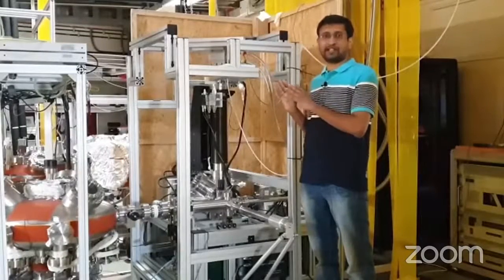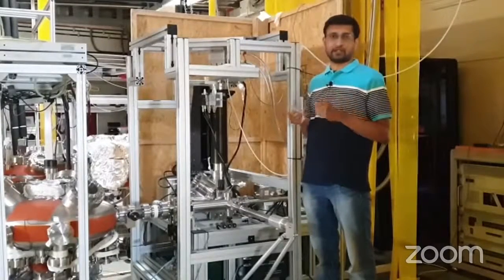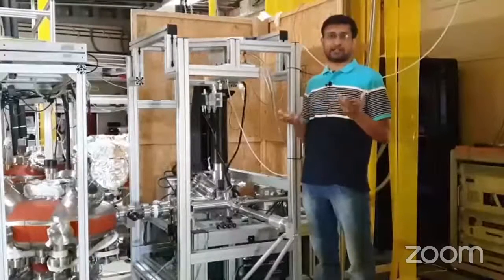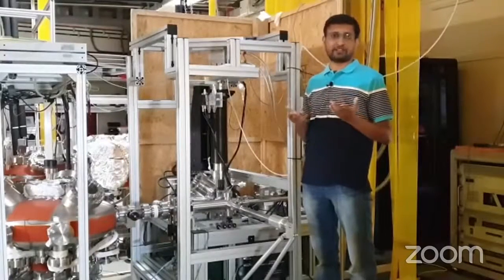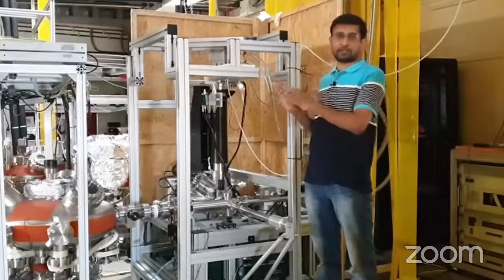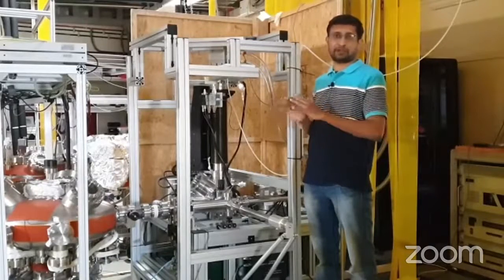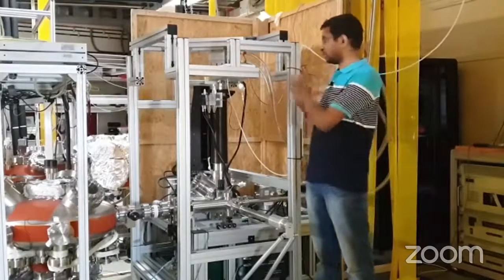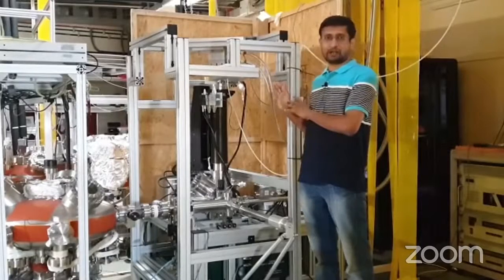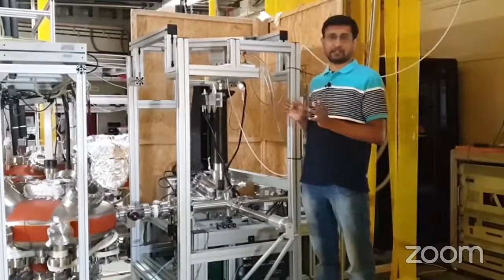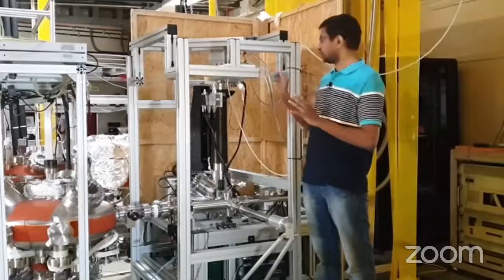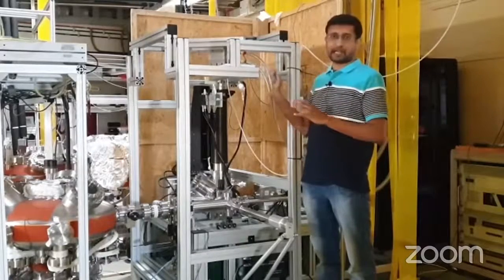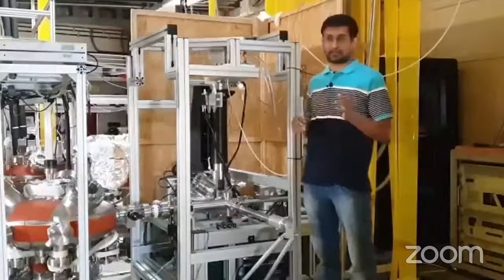That's one of the things that is special to this system, where to be able to go down to this low temperature, you don't need any liquid cryogenics. You need typically liquid nitrogen and liquid helium, which are very expensive, to really cool down your system and maintain it at low temperatures for a very long time. But with the facility that we have right now, we really don't have to worry about these liquid cryogenics. We can go to low temperature using a cold head technology and constantly measure 24/7.